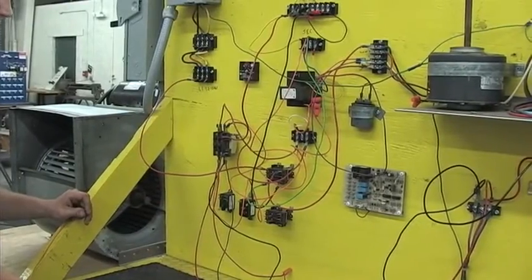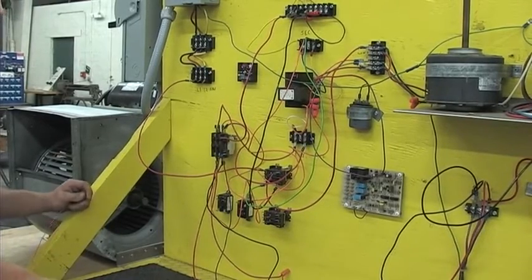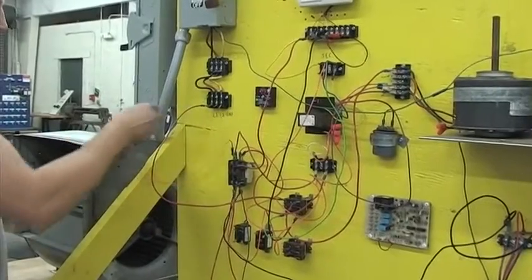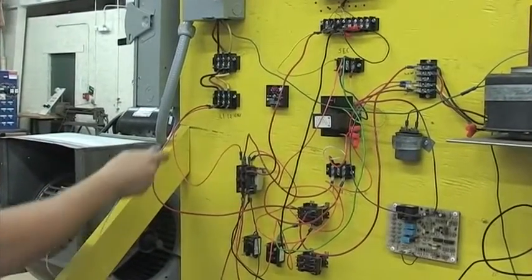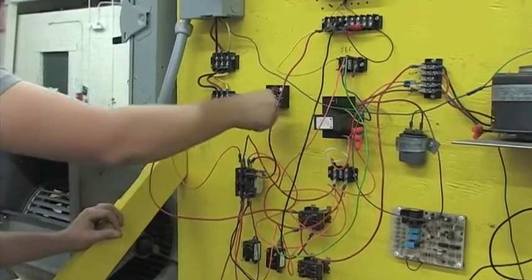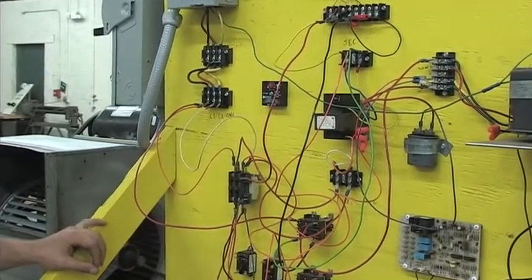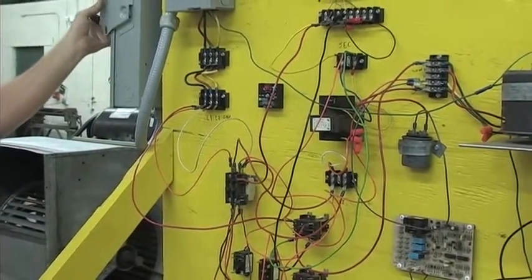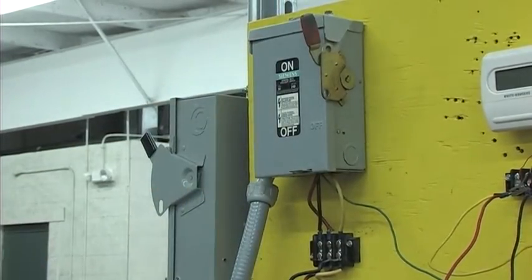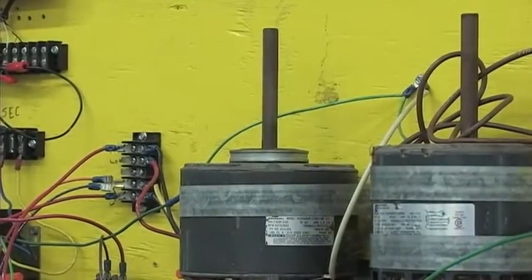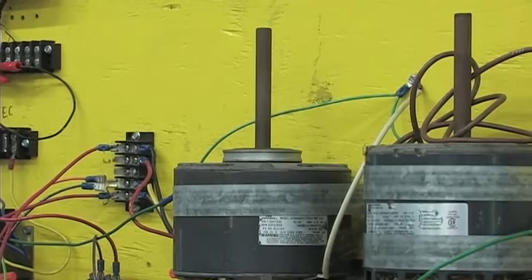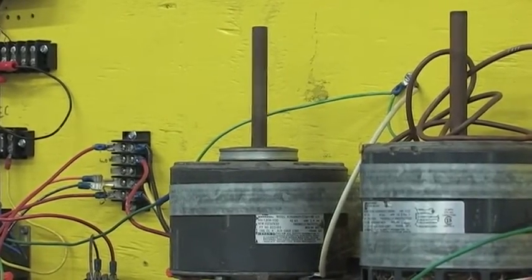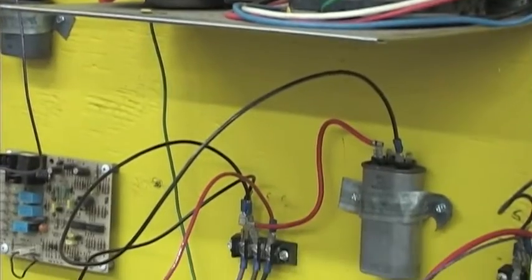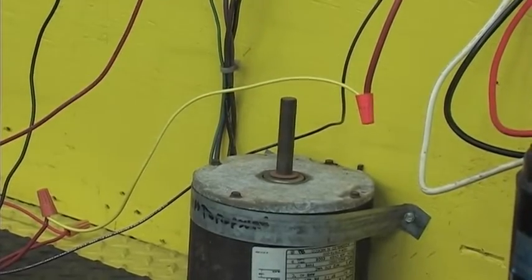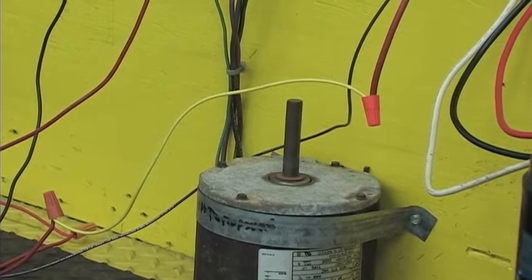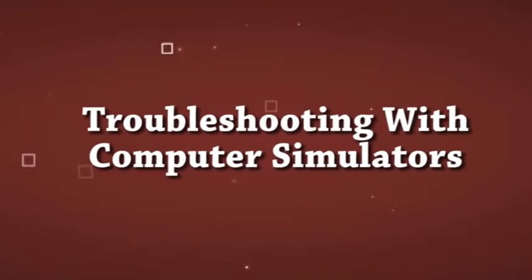Today Adam has wired the electrical board with the components. He's adding the last two wires. He's connecting L1 to the line side of the contactor, L2 to the line side of the contactor. Once he's completed this, he will throw both disconnects and operate the equipment. Once the disconnects have been energized, the motors come on, and in your home or office or wherever, there would be blades connected to these fan motors, which would move the air to remove heat or to add heat to the conditioned space.